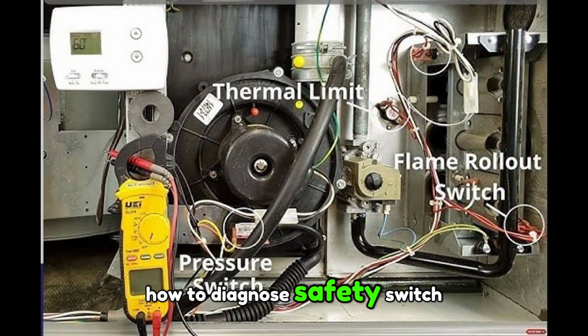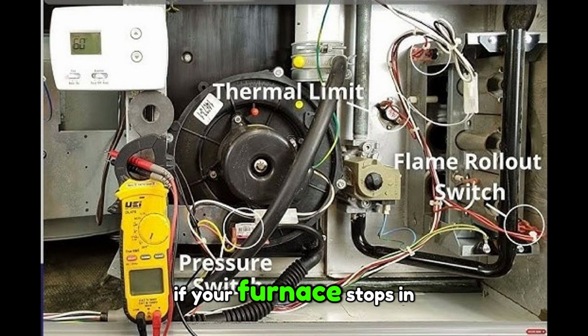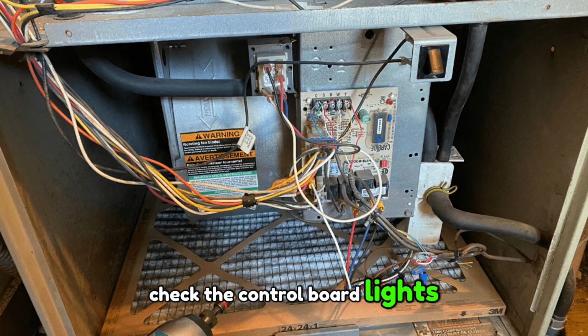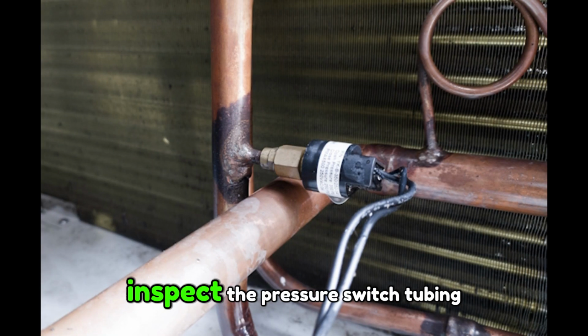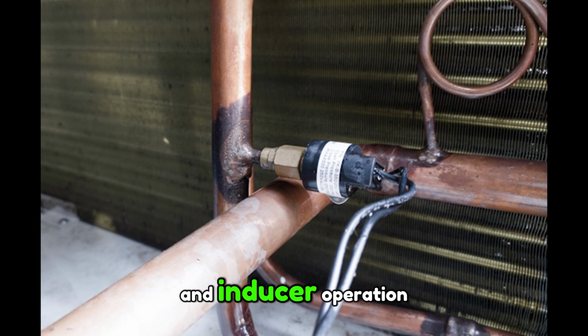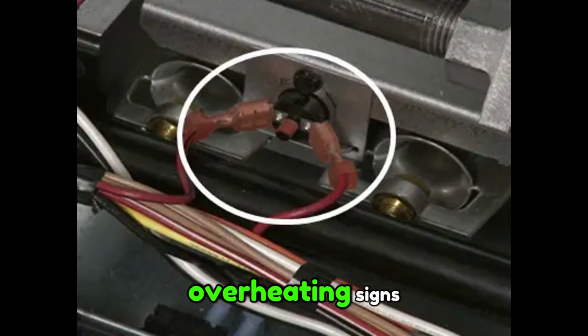How to diagnose safety switch issues. If your furnace stops in the middle of a heating cycle or never ignites, follow this checklist. Check the control board lights. Count the flash codes. Inspect the pressure switch tubing and inducer operation. Test the rollout and limit switches for continuity. Watch for flame rollout or overheating signs.